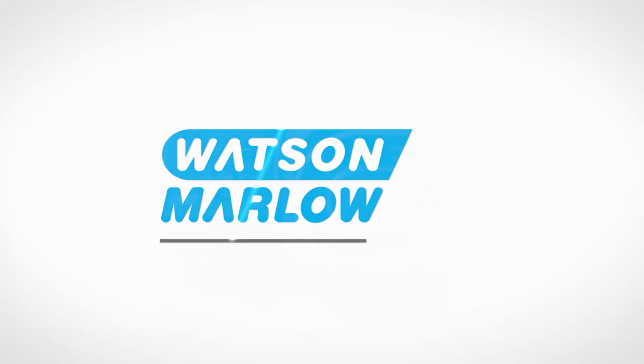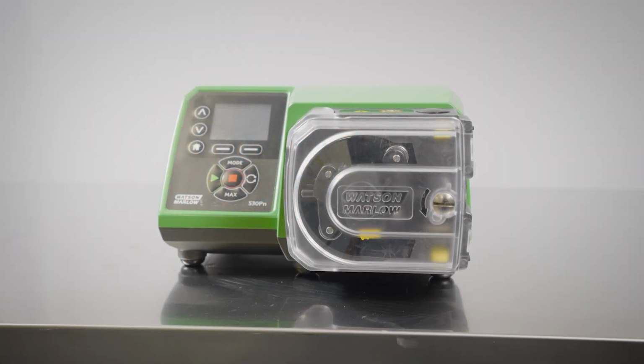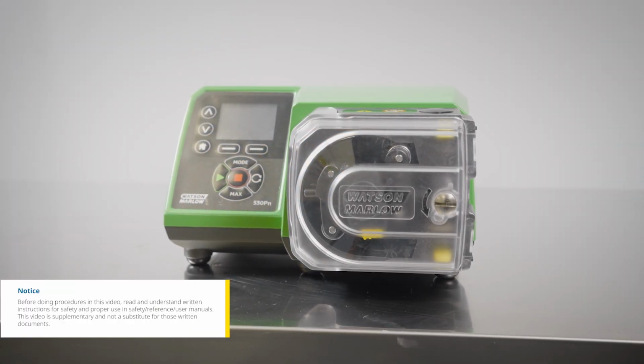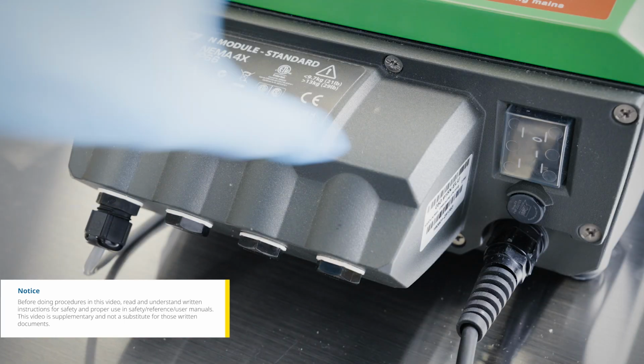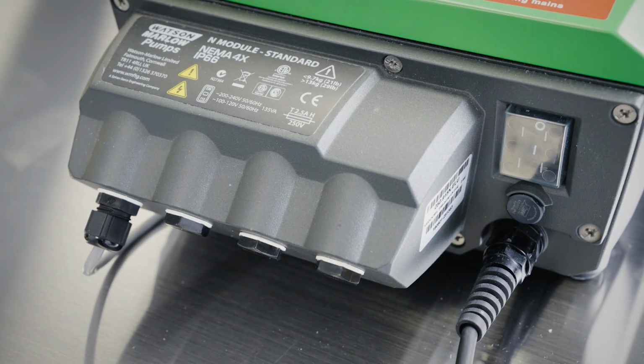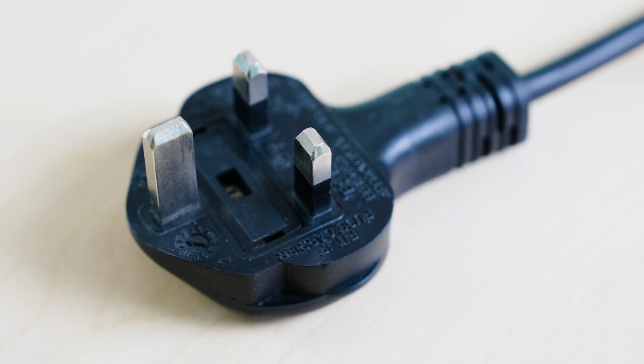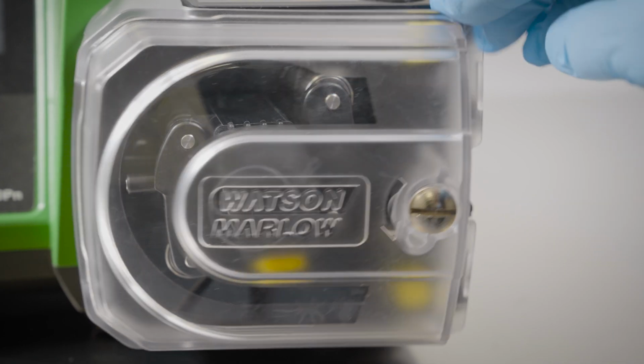In this video, we're going to show you how to install or replace a continuous tube in a Watson-Marlow 520R and R2 pump head. To begin, always isolate the pump from the mains power supply and isolate your process control signals and fluid connections. Unlock the guard with a flathead screwdriver.